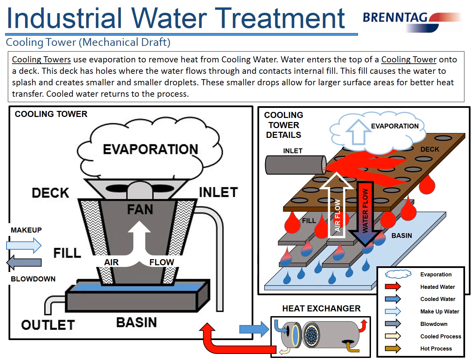In the operation of a cooling tower, we have what is called makeup. This is water that comes into the tower to replenish water lost through evaporation or water lost from leaks through the system. Brenntag sells a number of products that prevent scale, corrosion, deposit, and biological action within these systems. However, at some point, the water becomes too contaminated and must be removed, and this is done through what's called blowdown.